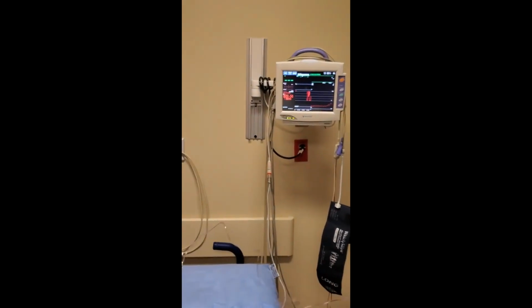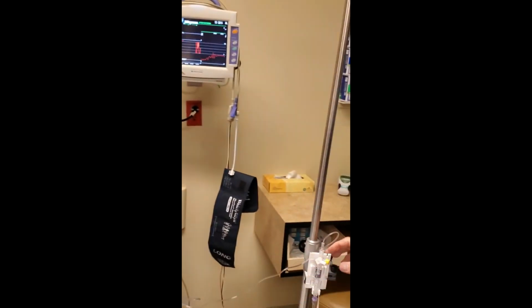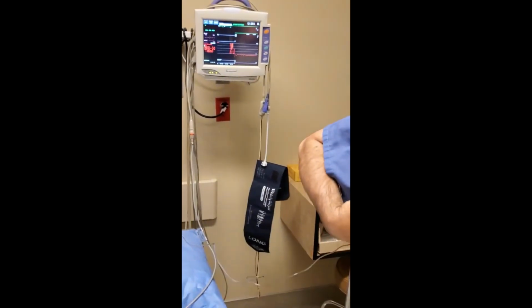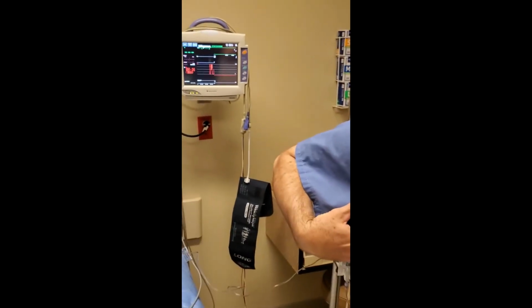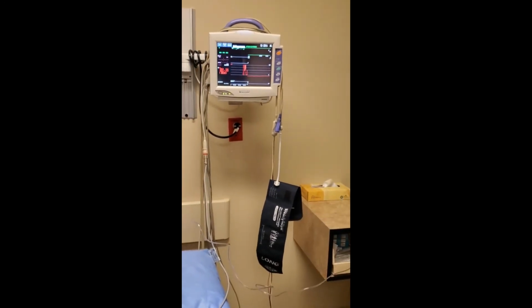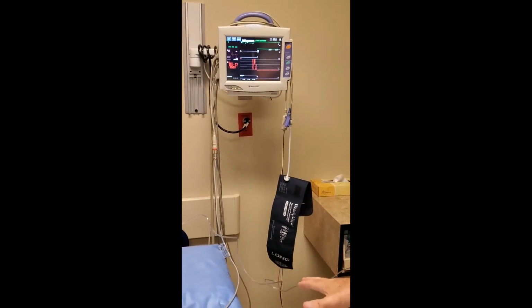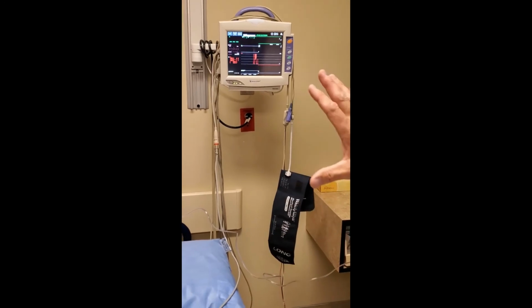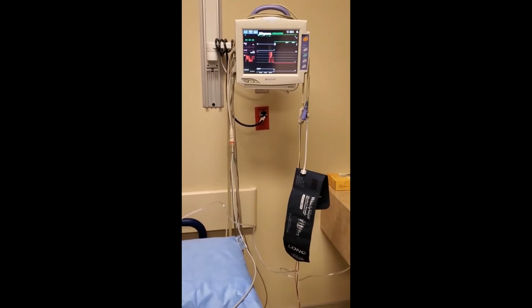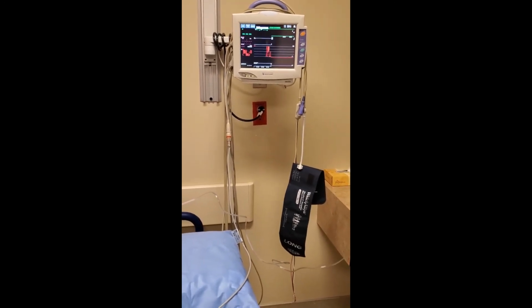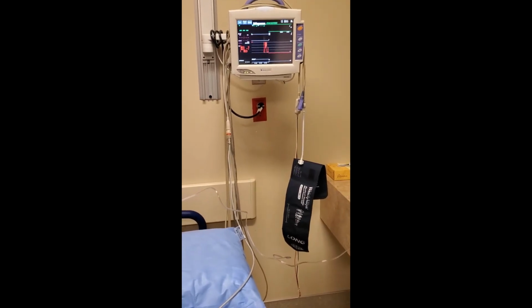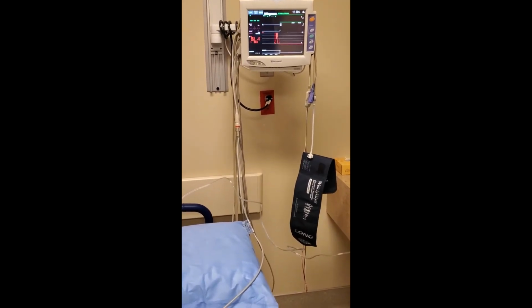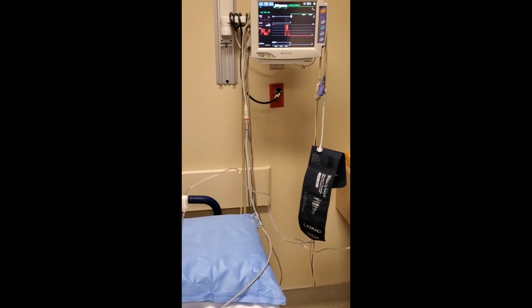So that's why you want to have this zeroed. You want to put it in one spot, level it with the phlebostatic axis, and then keep it there. If you adjust your patient's head down, that's going to change the pressure; if you adjust their head up, that's going to change the pressure too. So you always want to keep in mind, before you take your readings, where your patient is in relation to this. You'll be re-zeroing frequently just to make sure you're happy with the numbers, especially if the patient's pressure has been 120 and now it's 70.